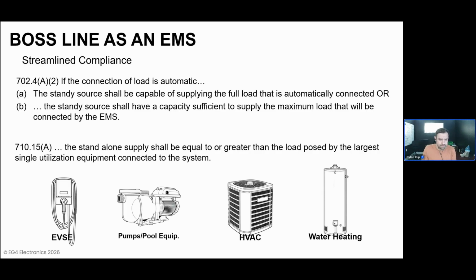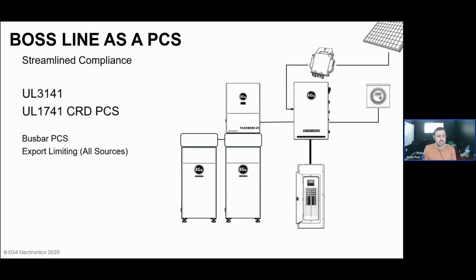And then the BOSS line can also act as a power control system, or a PCS. We really do this through compliance with two different standards, both of which are kind of the same standard. Actually, there's a shift from the traditional UL 1741 CRD for PCS over to UL 3141. I only mention this to say you can find certification documentation for both of these standards on the EG4 website, but there's really two critical functionalities that are met by the system as a power control system.